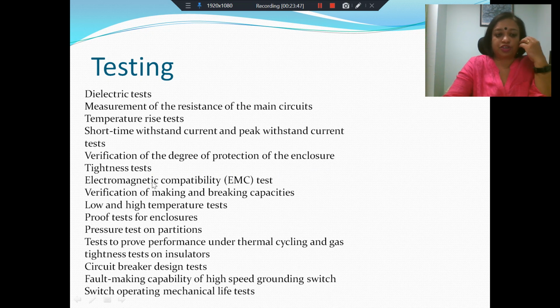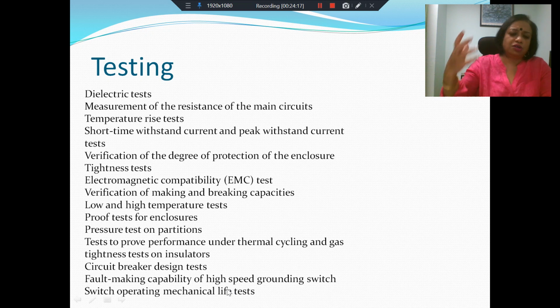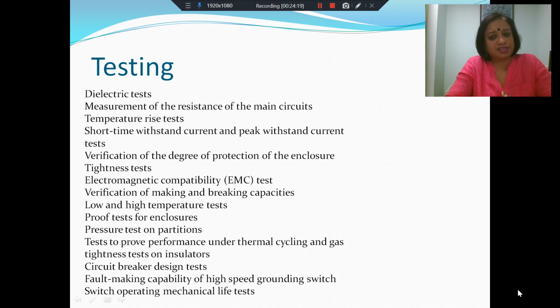electromagnetic compatibility test for safety of equipment and personnel outside, verification of making and breaking capacities, low and high temperature test, proof test for enclosure, pressure test on partition, test to prove performance under thermal cycling and gas tightness tests on insulators, circuit breaker design test, fault making capability of high-speed grounding switch, switch operating mechanical life test. So there are a whole lot of tests that need to be done. These are generally type tests. There are routine tests which also need to be done.